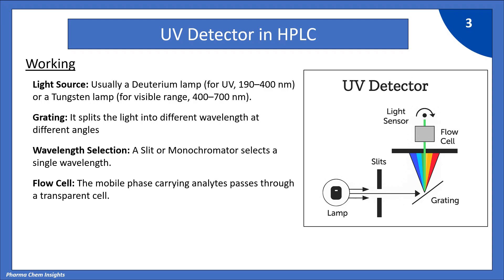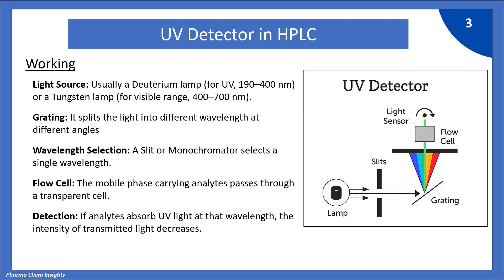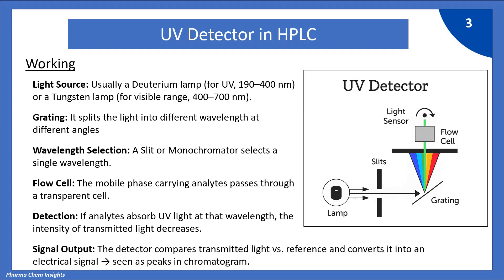The flow cell is the compartment through which the mobile phase carrying analytes passes. When the analytes enter the flow cell, they can absorb the light falling onto them. If analytes absorb UV light at that wavelength, the intensity of transmitted light decreases. The absorbed light is measured by the light sensor. The detector compares transmitted light versus a reference and converts it into an electrical signal, which appears as peaks in the chromatogram.